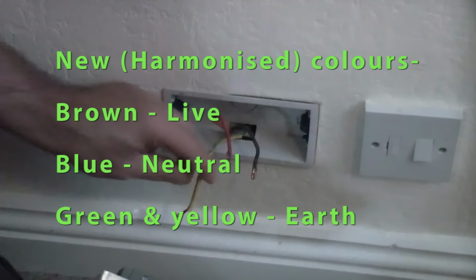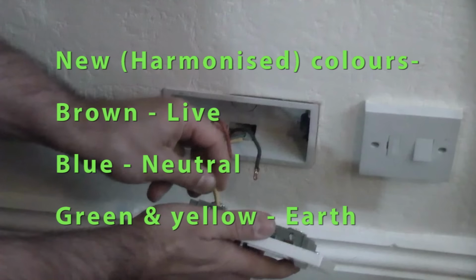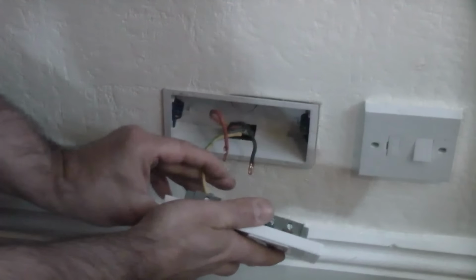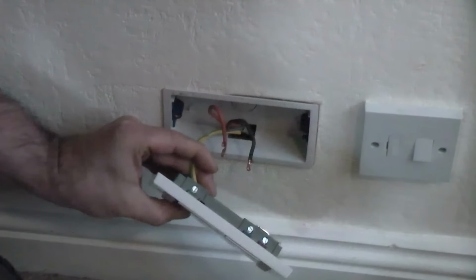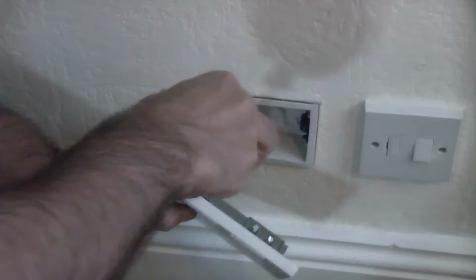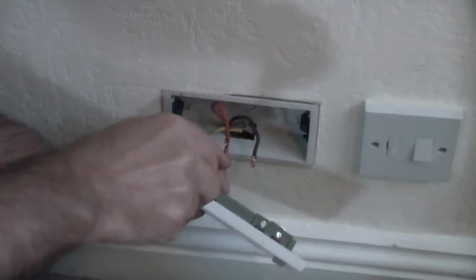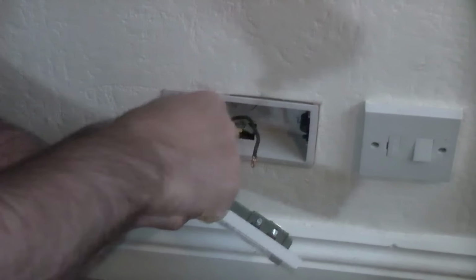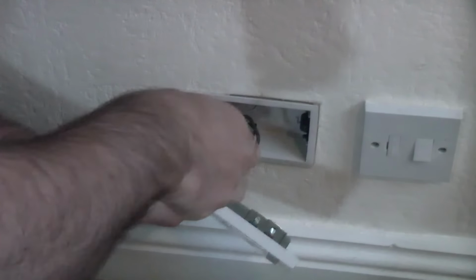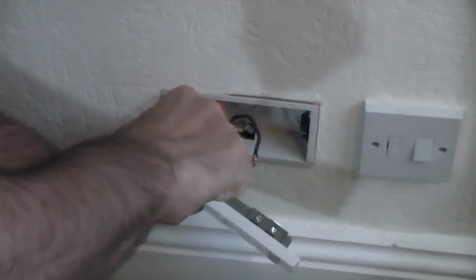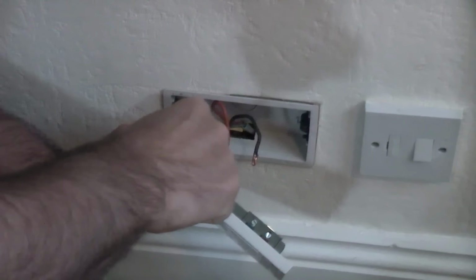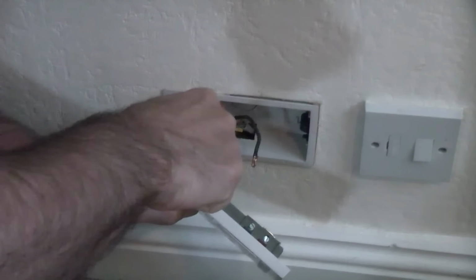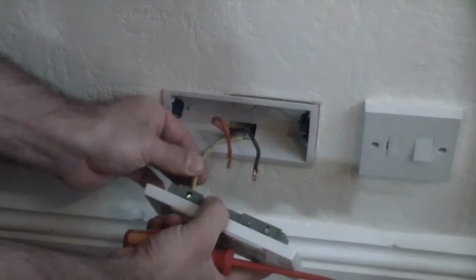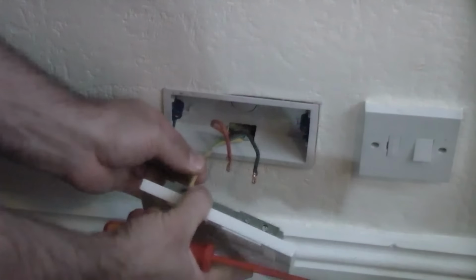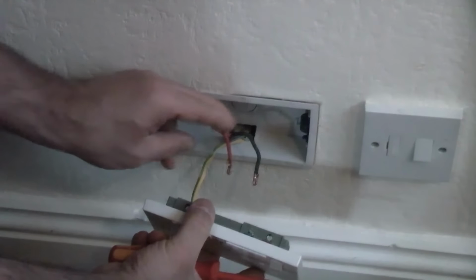I'm just going to pull that around, and then put that into the earthing terminal and tighten that up. These terminals do need to be tight, but not so tight that you're actually going to sever the wire. Once that's in, just try giving it a pull and ensure that you can't pull it back out.